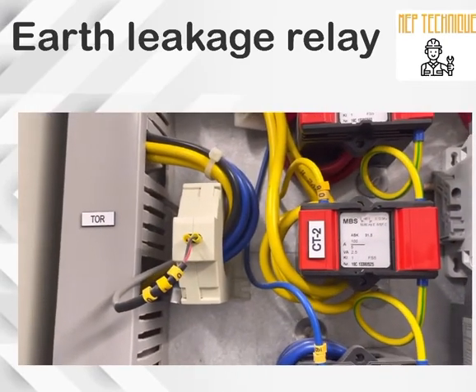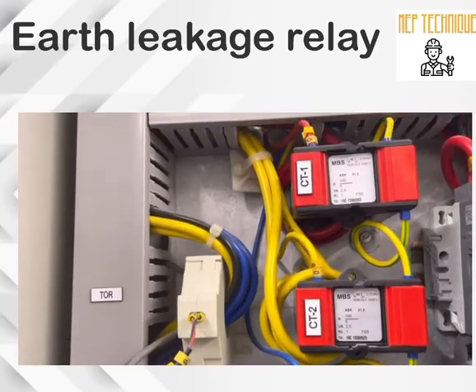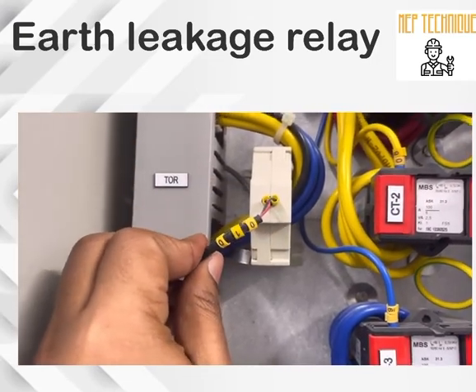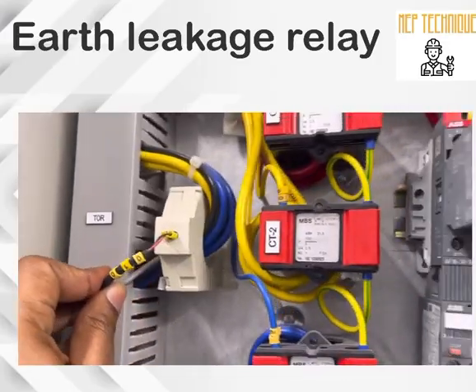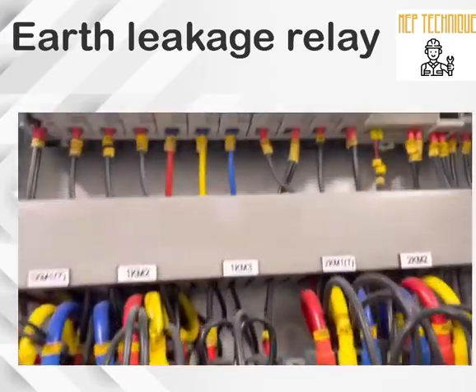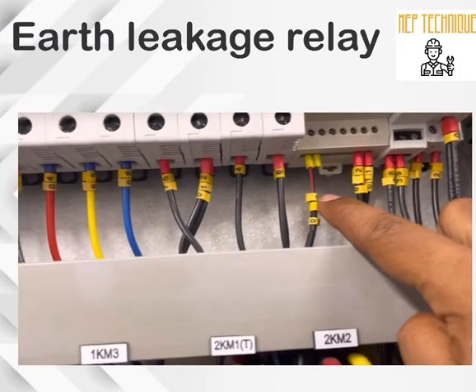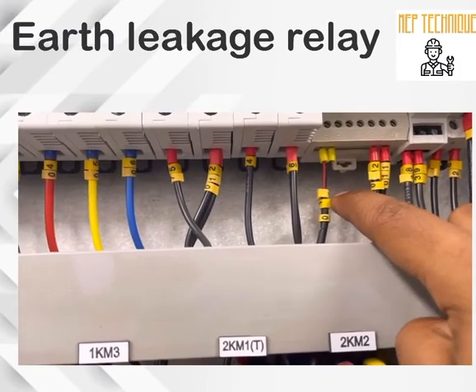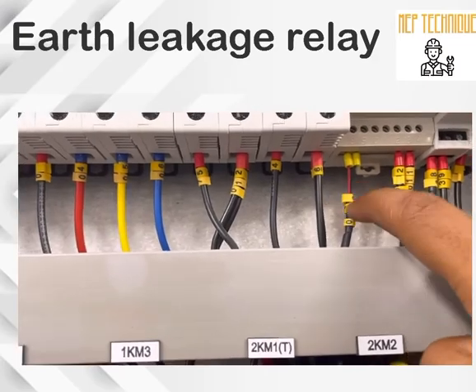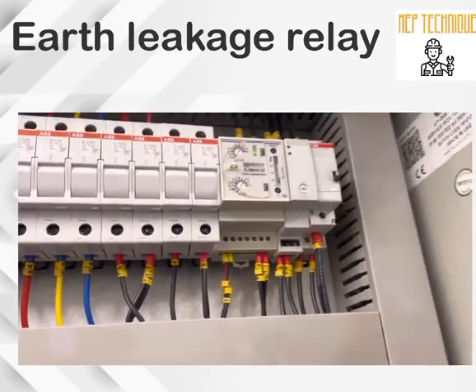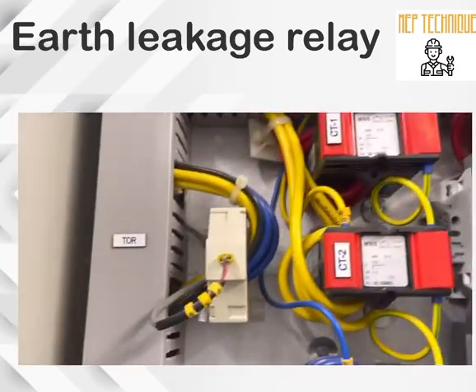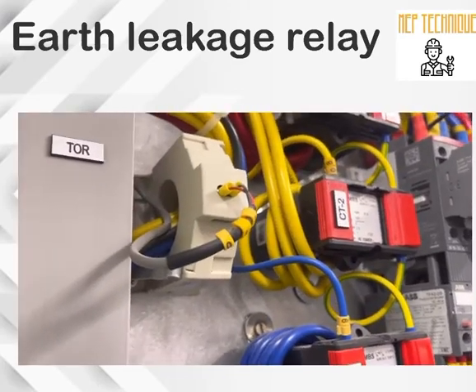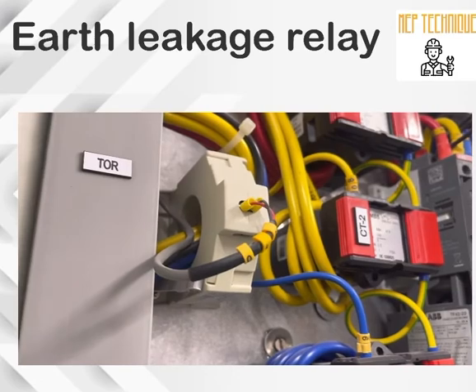This is the CBCT — core balance current transformer — that we discussed previously. It is installed over the three-phase cables: R phase, Y phase, and B phase. The red and black cables are connected with the earth leakage relay. If there is any imbalance current, this CBCT will sense it and the earth leakage relay will trip our MCCB.